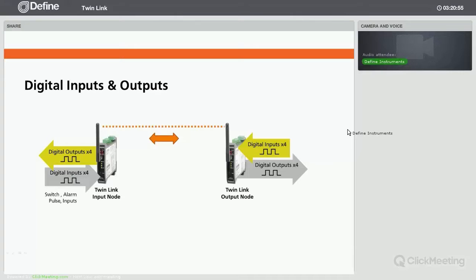Let's look more closely at the digital inputs and outputs. The TwinLink can accommodate up to 4 digital inputs. These may be a pulse input or an input from a flow meter or a level switch, for example. They can even be a closed contact relay or an output from a PLC. The TwinLink takes these inputs, transmits them wirelessly, and outputs the complete mirror of the inputs. This allows you to remotely control and monitor without the need for cabling. You will notice that the signals can go both ways for the digital outputs and inputs, and this is great for monitoring interlocks or confirming the alarm has reached its destination.